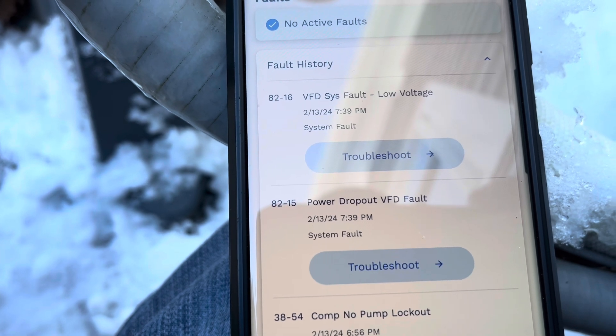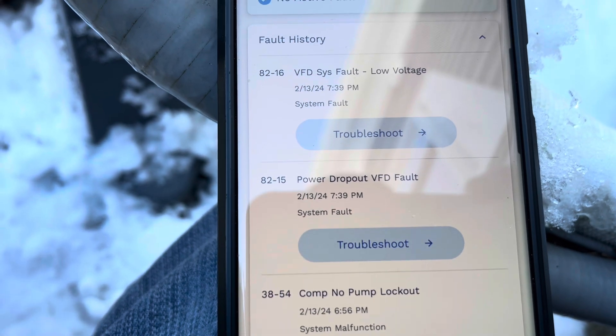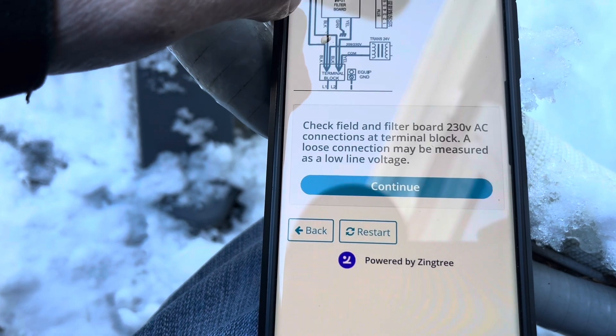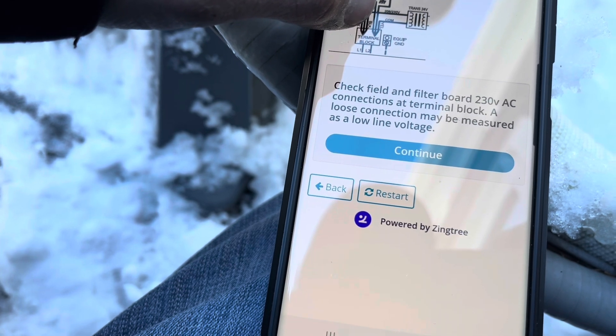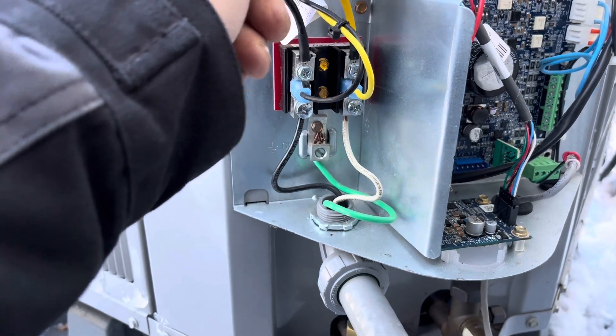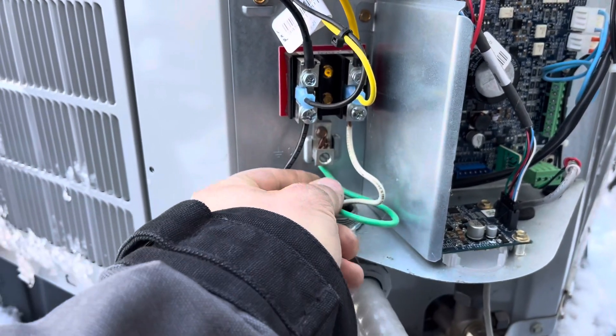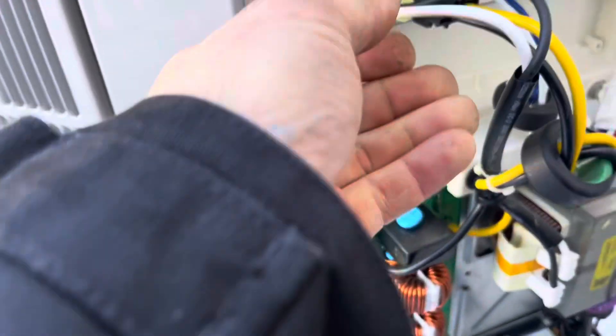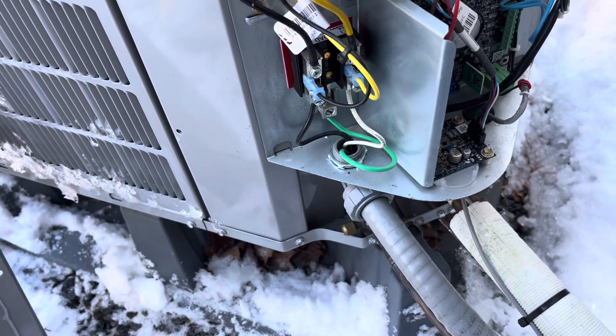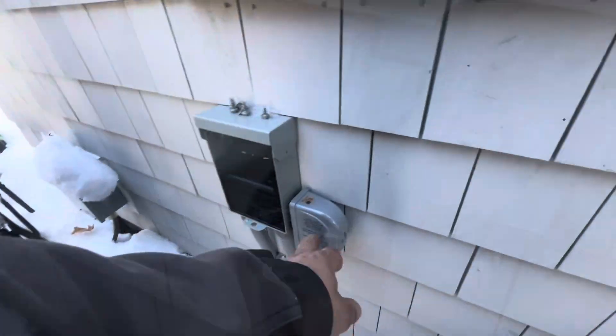He had a drop in power — all in the same couple of minutes. I'm going to throw a surge protector in here for him anyway. Check field and filter board — connection on the terminal block is loose. The connection may be measured as a low line voltage. Let me check over here. I'll tighten all this stuff up for him and throw this on, then power it up.